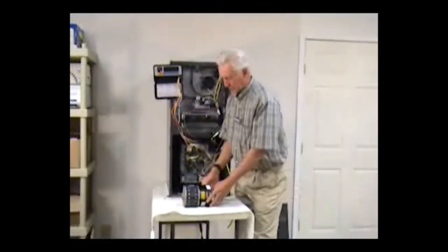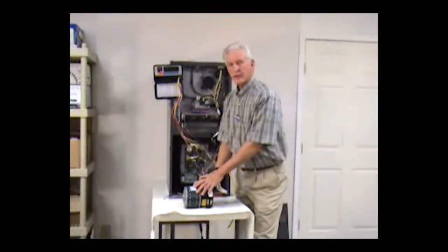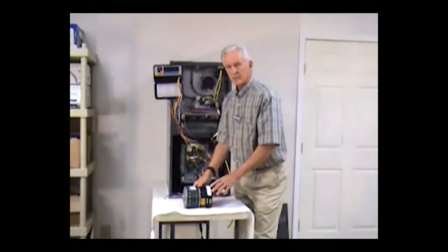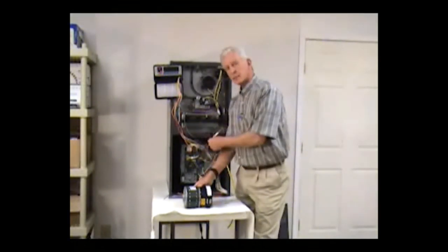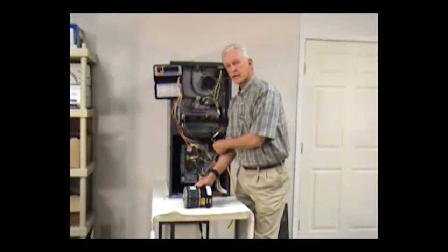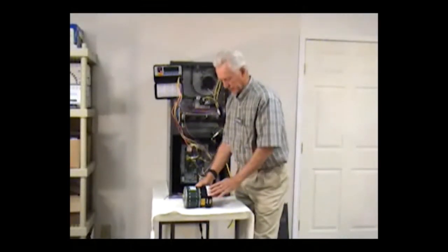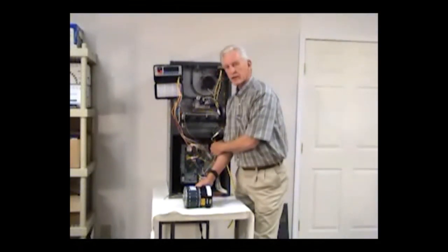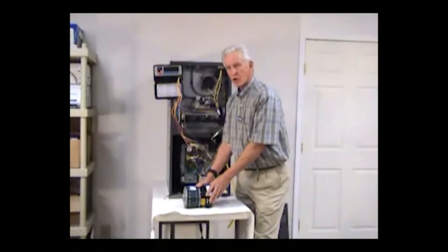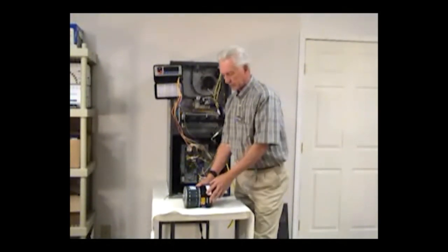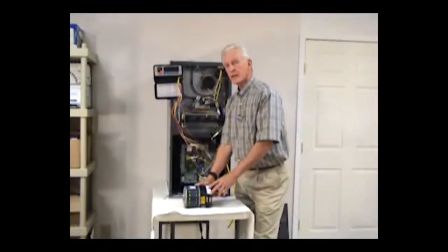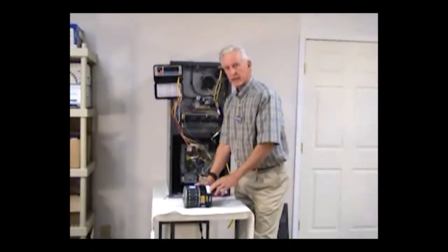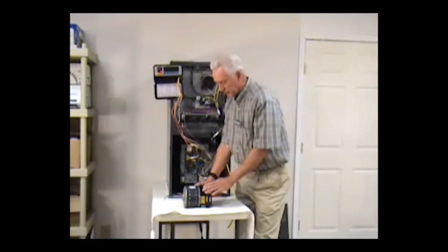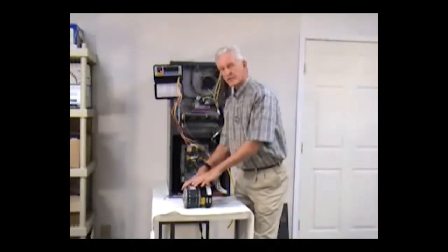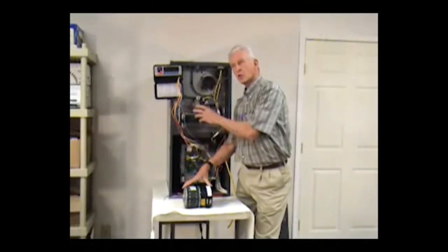The modules that are attached to the motor itself, even though the motor is 120 or 240 volts, a specific module to that motor and to its application in either a furnace or an air handler have to be kept correct. In other words, module to motor to specific air handler. The modules are programmed either by the manufacturer of the motor itself or through some manufacturers who have the authority and the rights to be able to program the module itself.